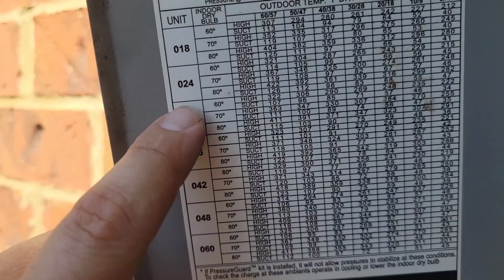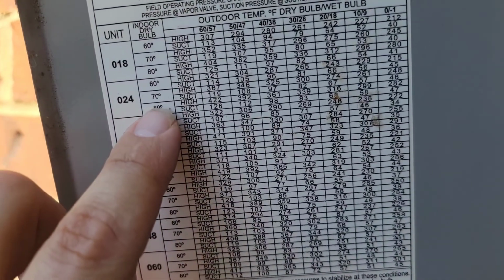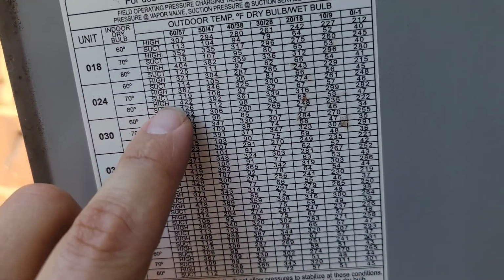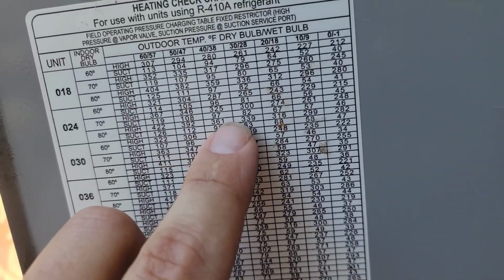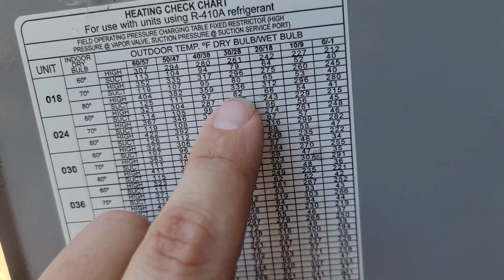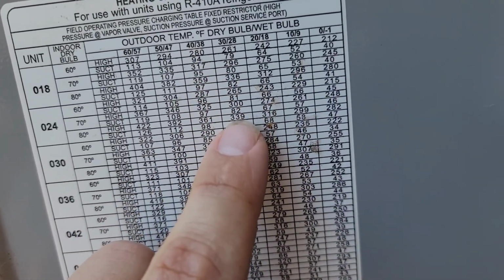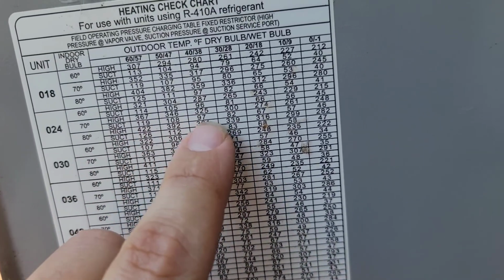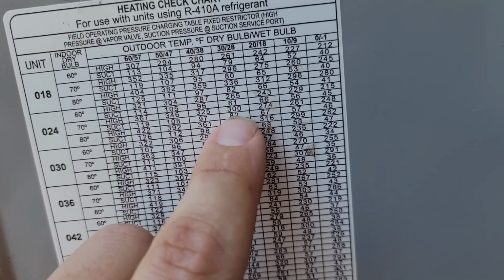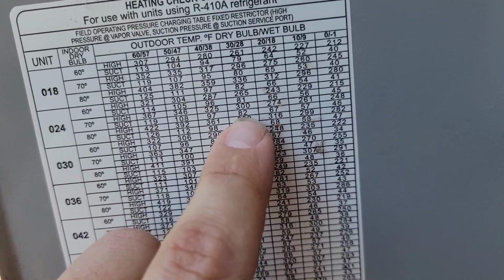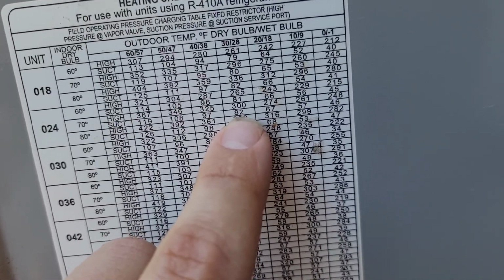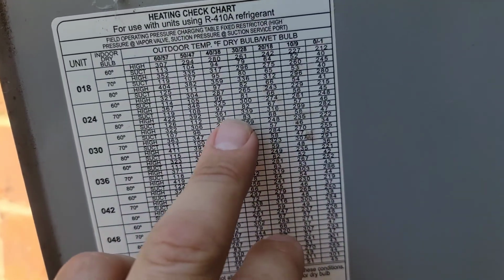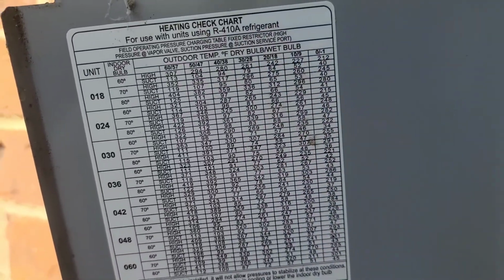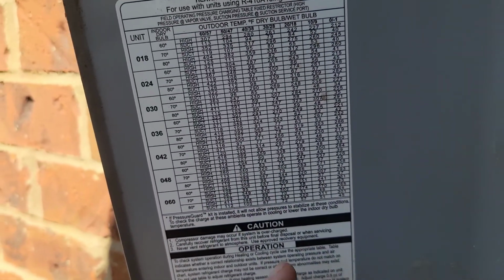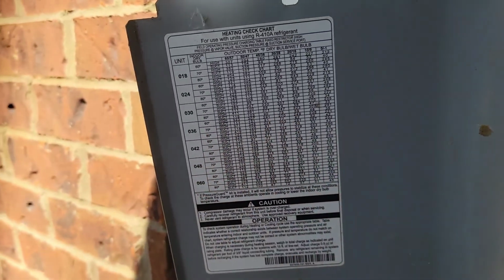We've got a 024 unit. We got about a 70-degree indoor dry bulb. It was 72. If we scroll over, it's about 30 degrees outside today. So if we scroll down and we go look at this column, our high side pressure should be about 300 and our suction pressure should be about 82. And you can see we had about 60 and 325. So we're a little bit off, but these charts are great.